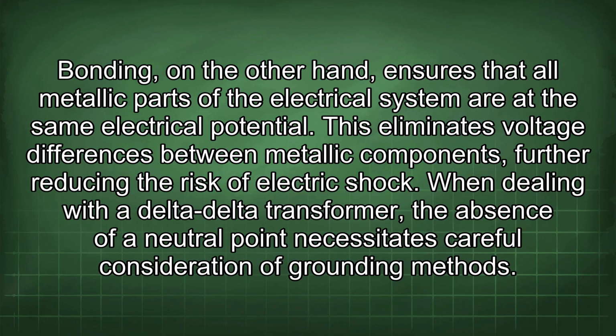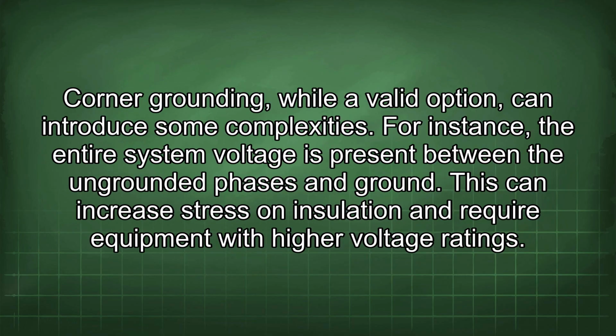When dealing with a delta-delta transformer, the absence of a neutral point necessitates careful consideration of grounding methods. Corner grounding, while a valid option, can introduce some complexities. For instance, the entire system voltage is present between the ungrounded phases and ground. This can increase stress on insulation and require equipment with higher voltage ratings.